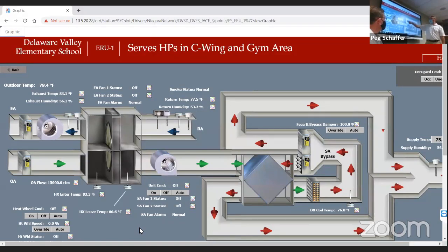The air coming back from each room is going through the heat wheel, giving us back that energy. So it's returning back through the wheel and into this side, and then we're exhausting it. Where in many cases, earlier we talked about the air returning back to the room, each room here is being exhausted through the energy recovery units, so all the classrooms actually have full-on exhaust. Now, Jack had talked earlier about negative pressure and different things. It is not a negative pressure unit, but the good thing is all that air is exiting. There are 2 large rooftop units up on the roof of that building that handle all the main classrooms. A few have smaller, different systems, but for the most part these rooftop energy recovery units serve the fresh air to the building.